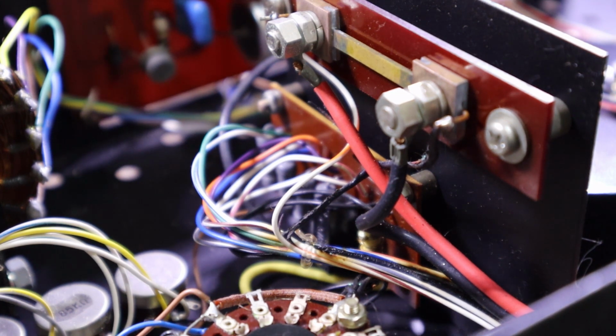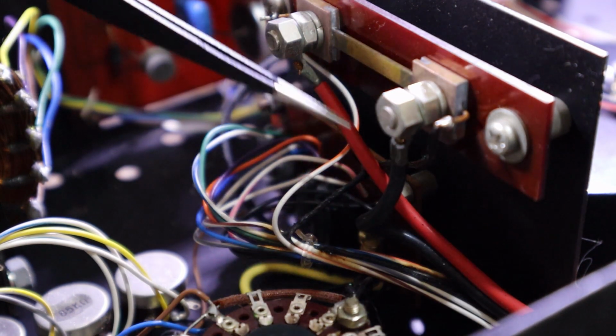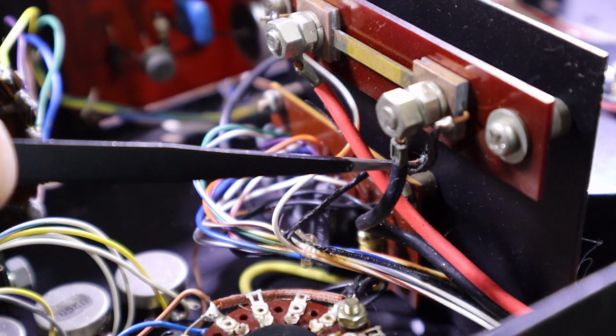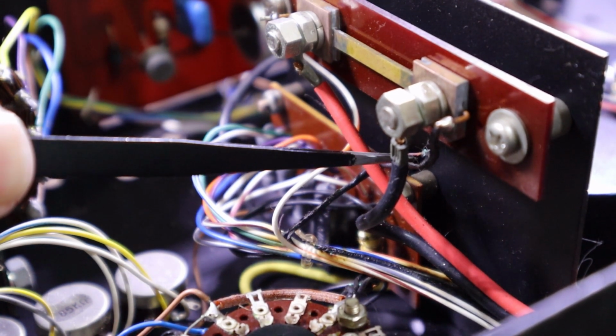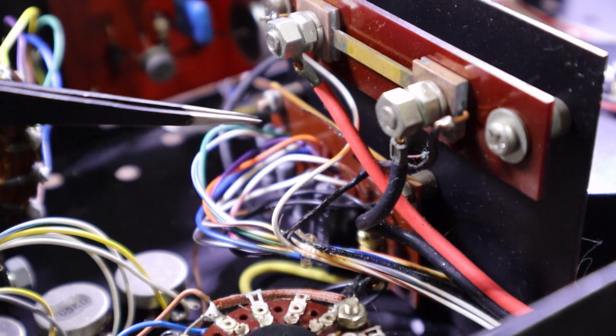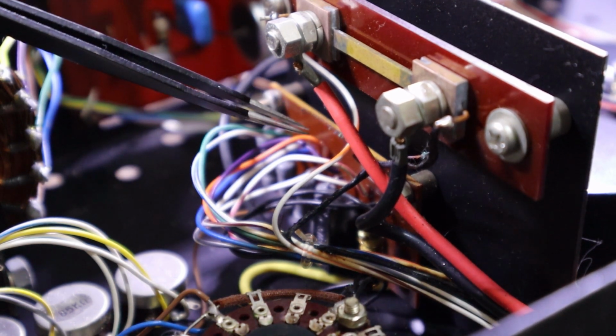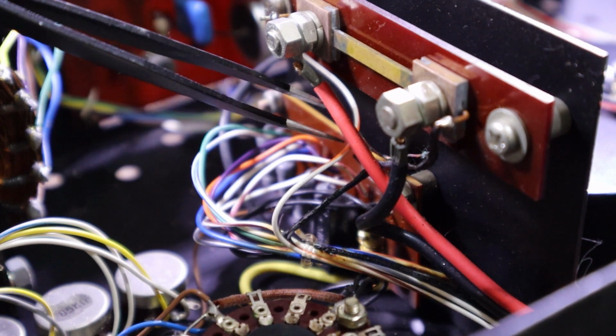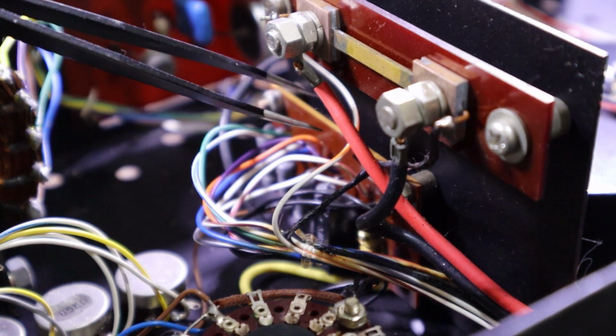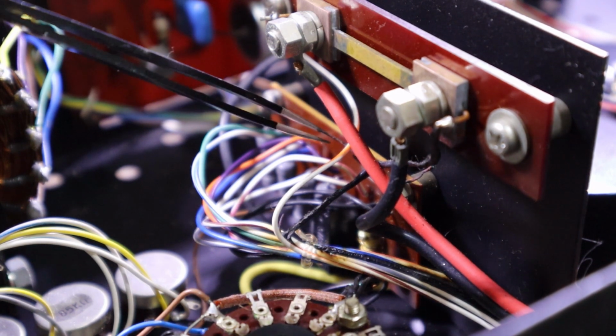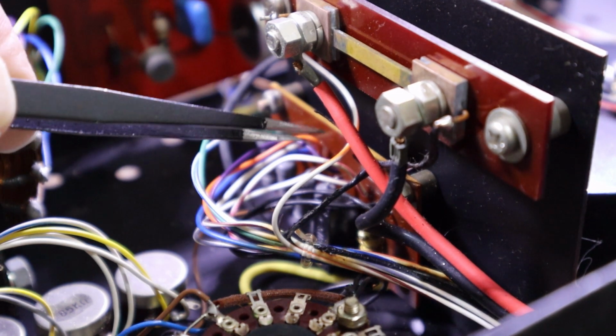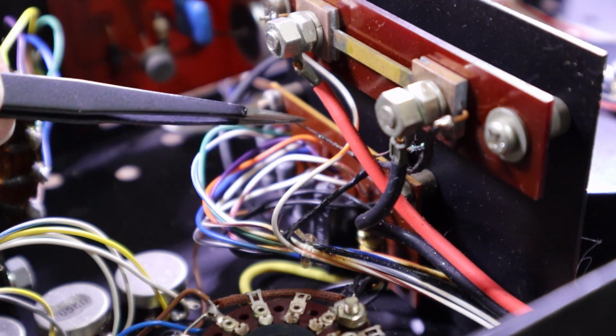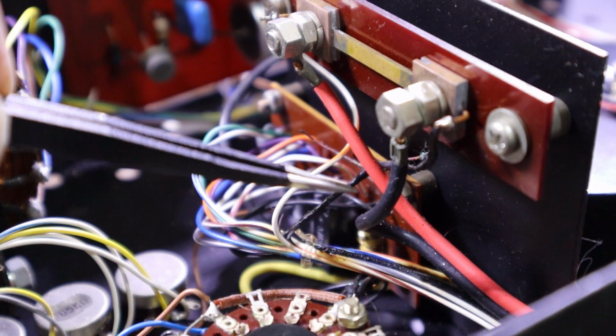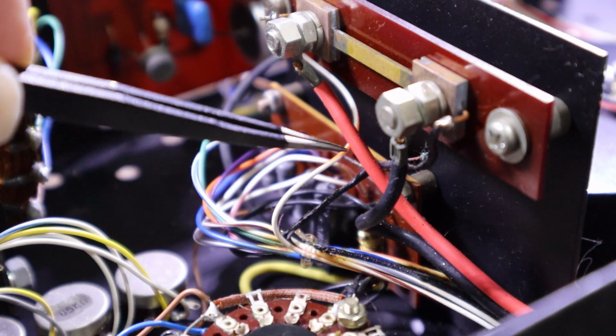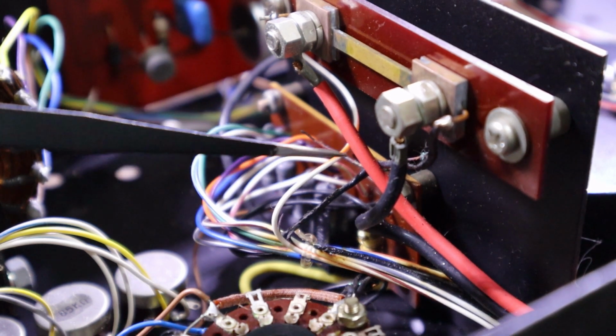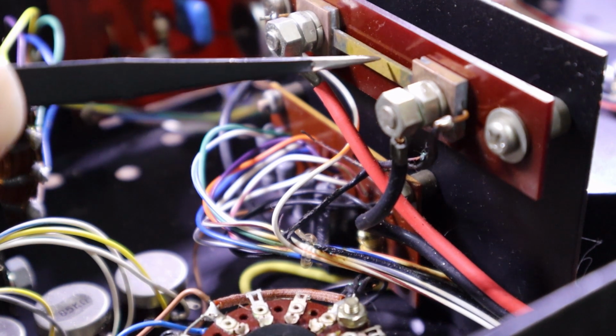Well, right off the bat I can see that there's a wire here that is melted. That one there is melted out. It's hanging, a strand's hanging out here. So it's actually clearly seen an overcurrent situation, and you can see that hanging out there. It's come out of the insulation, that black one that runs down here. So that's the sense wire off of our current shunt, of all things.